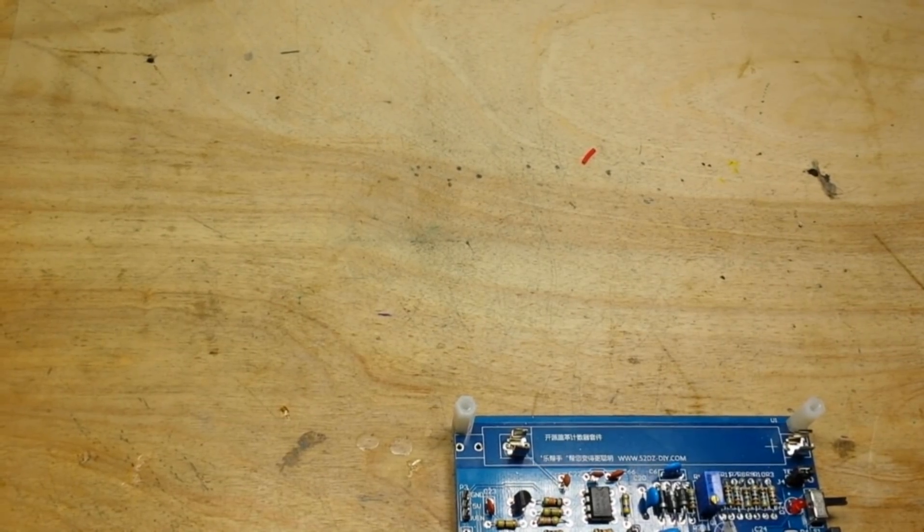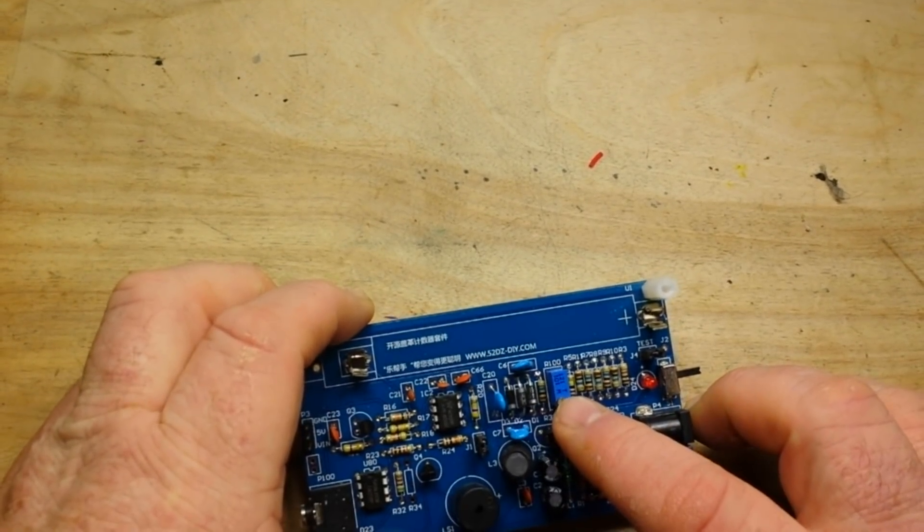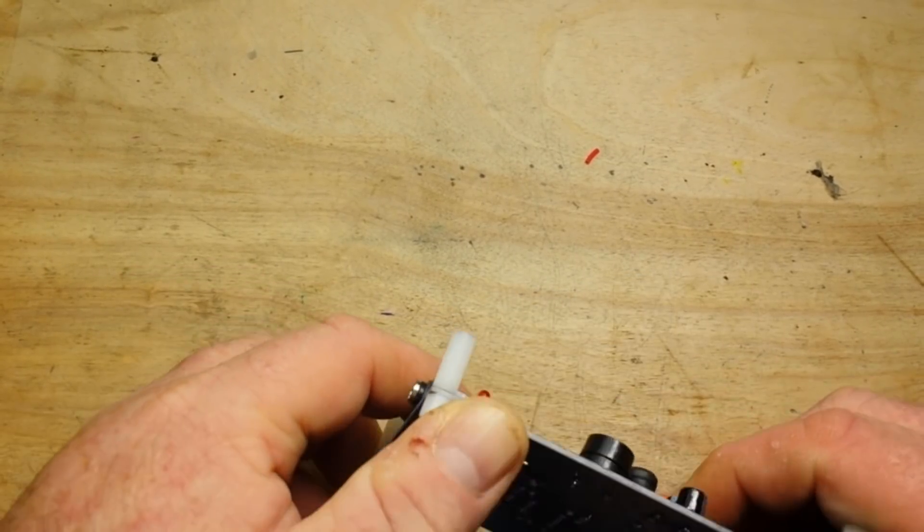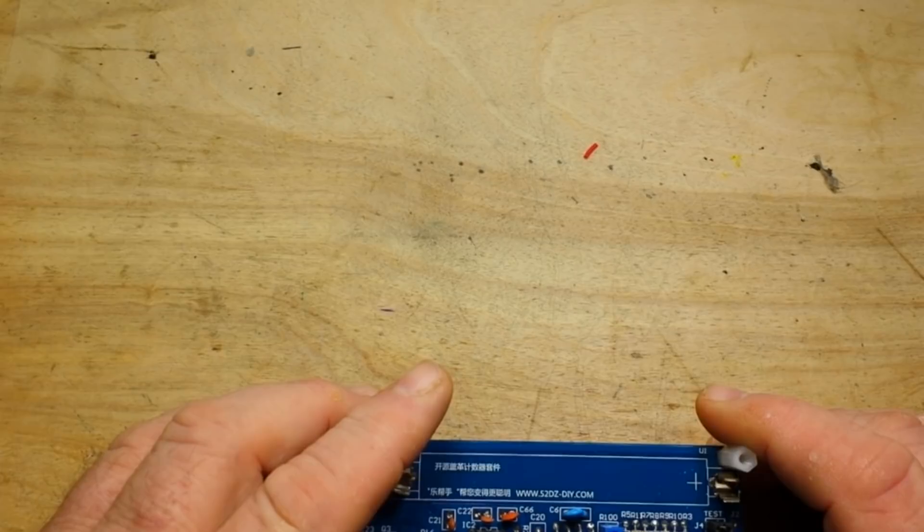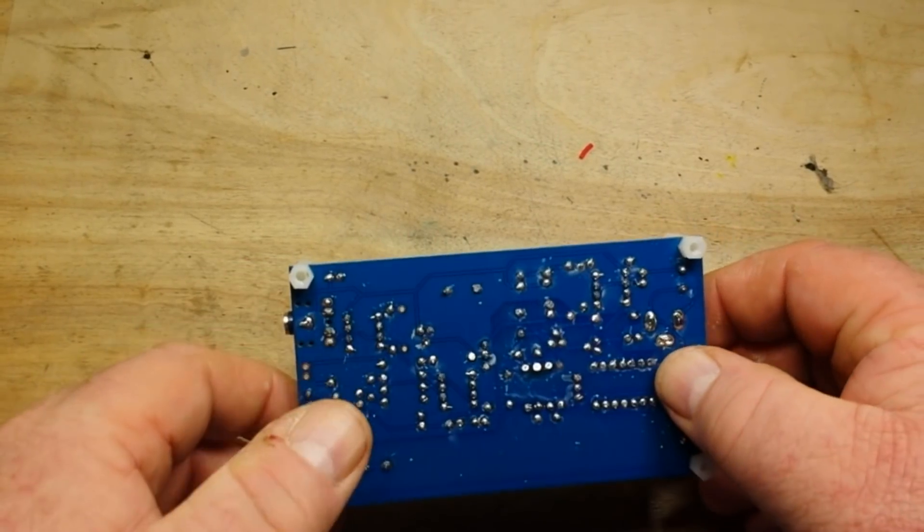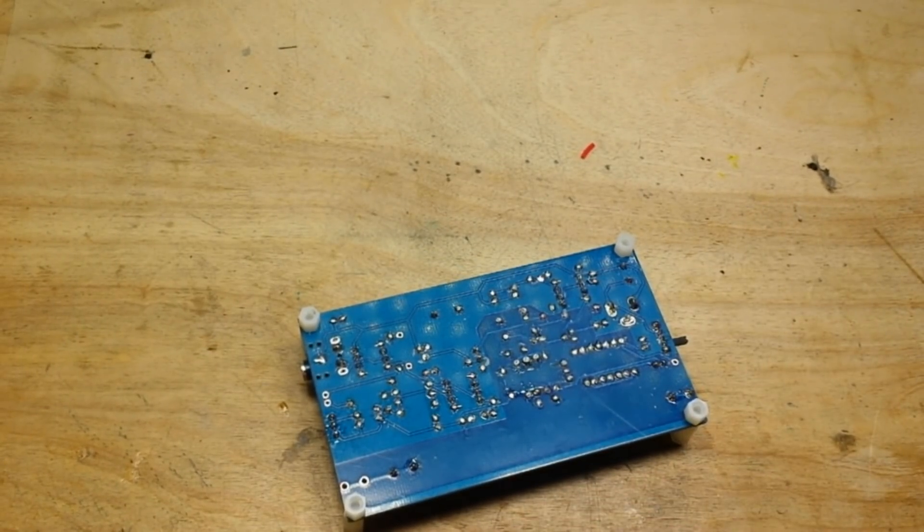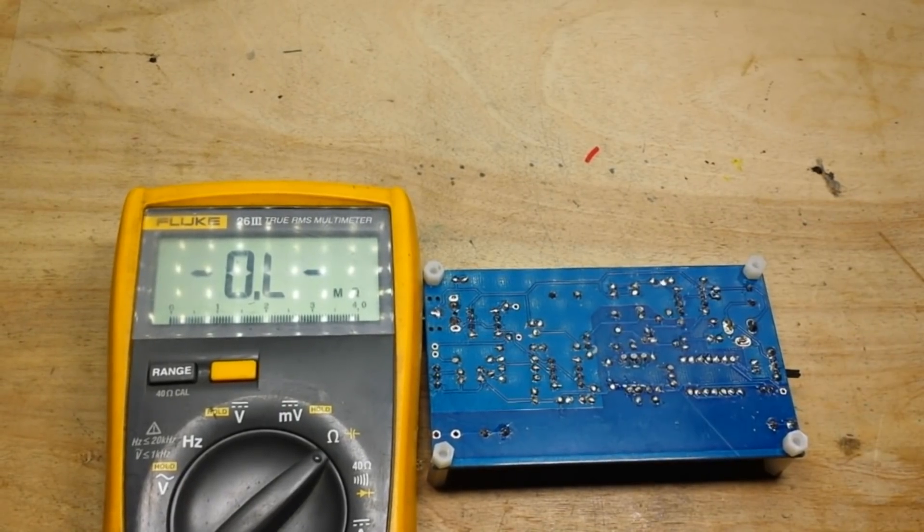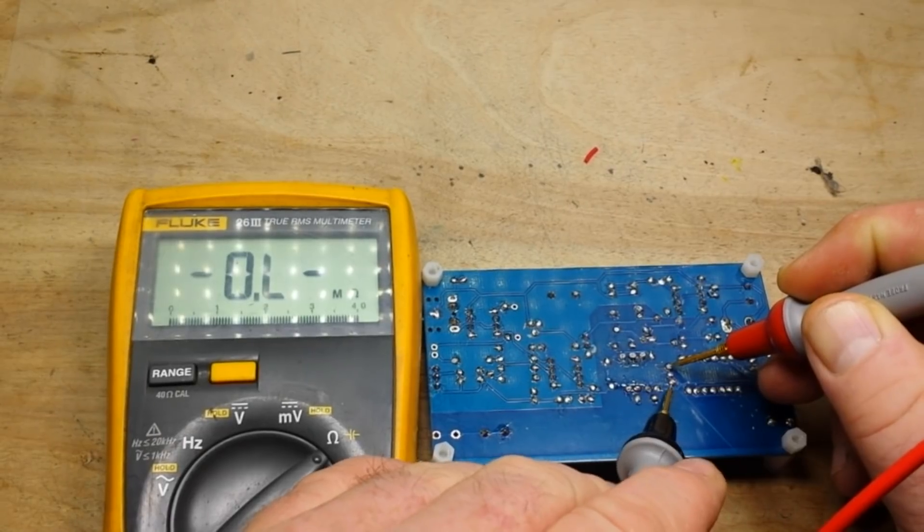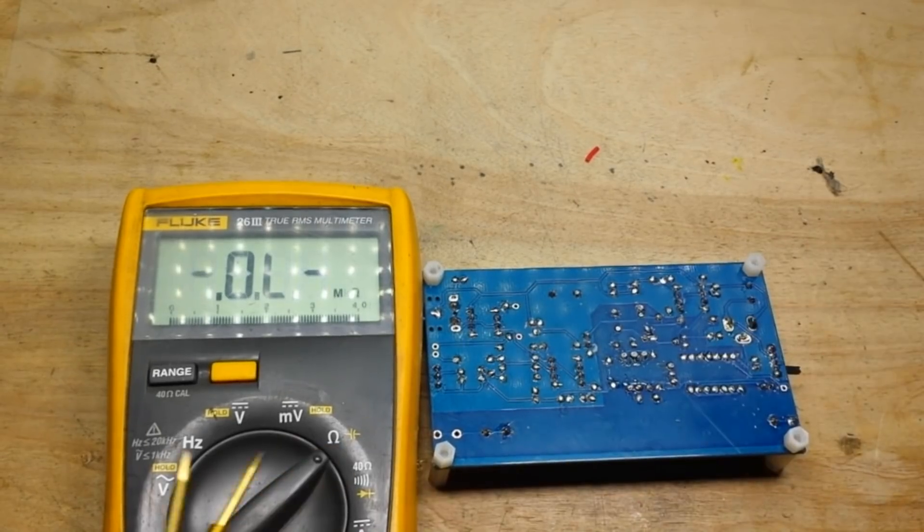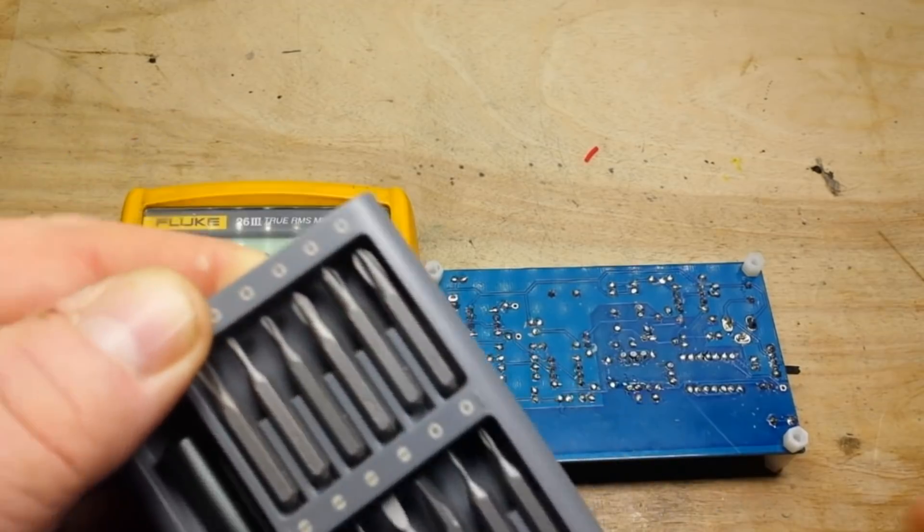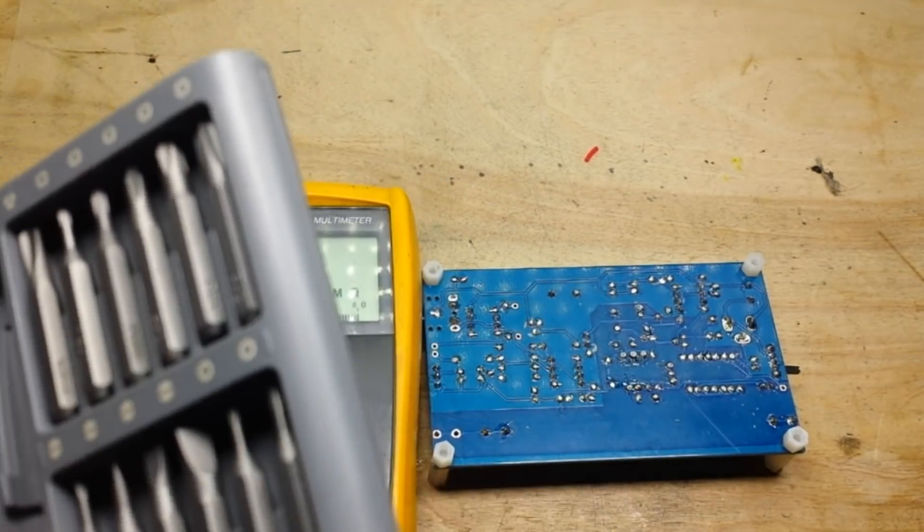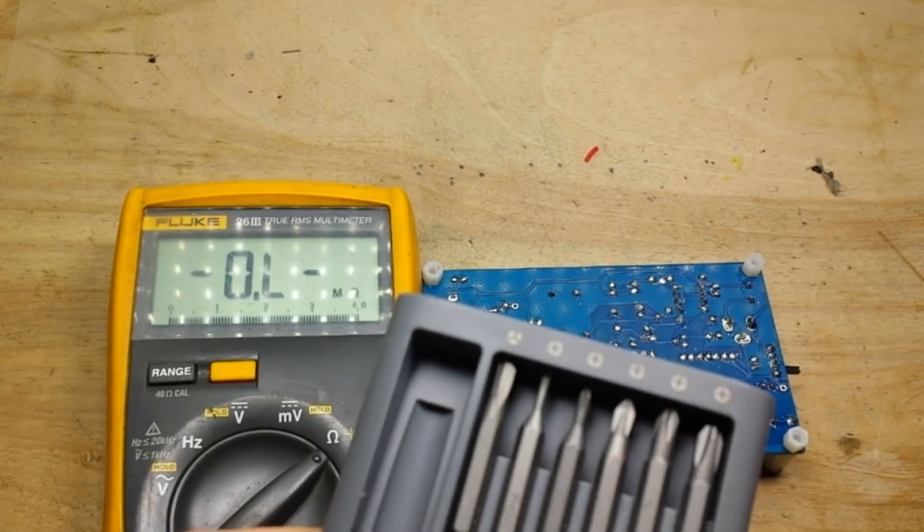This is R100 and we need to trim it to 50 ohms. Let's see where she's at right now. Bring in the meter, set for ohms. If we read across the outside we get 43.6 ohms out here and we will see if we can't trim that bad boy a little better.